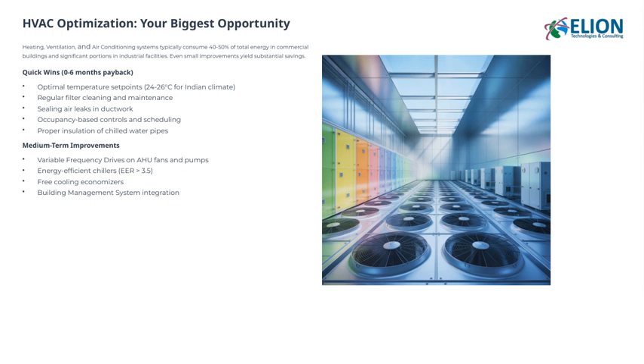Let me share a quick case study. An IT park in Bangalore undertook a comprehensive HVAC optimization, adding VFDs, upgrading controls, and replacing chillers. The result? They achieved a 38% reduction in cooling energy consumption, which translated into savings of about 45 lakhs rupees annually, with a payback period of just over a year.